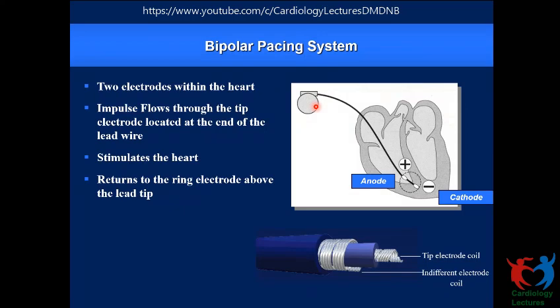And another important advantage is that because it's bipolar, if there is a fracture that develops, the most likely place the fracture can develop for the conducting wire would be at the junction of the clavicle and the first rib, where there could be some mechanical stress. If that happens, what will get affected first would be the outer insulation, and this mechanical stress would further transmit into the outer electrode, and logically it's the outer electrode that is likely to get affected first, whereas the inner insulation and the inner electrode may remain intact, in which case we can still convert this pacemaker into a unipolar configuration so that you don't have to rush in for an emergency lead change.